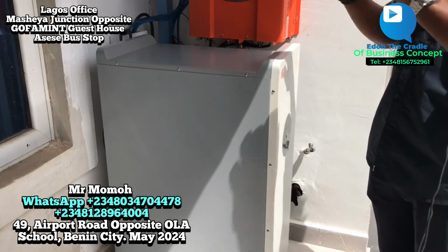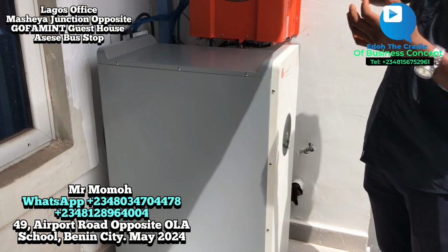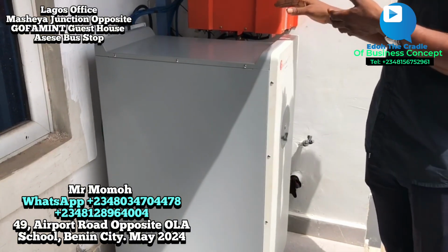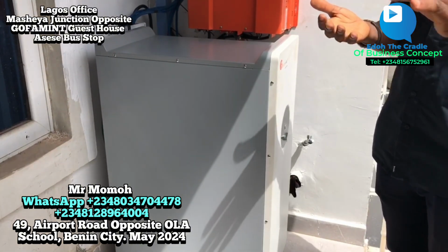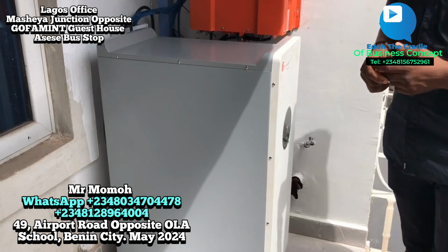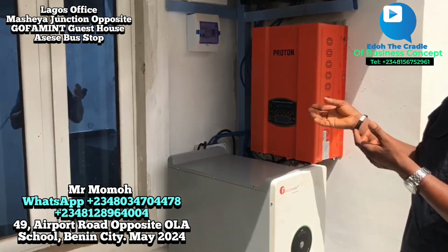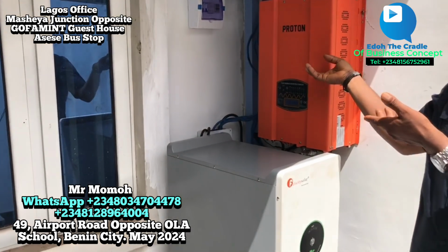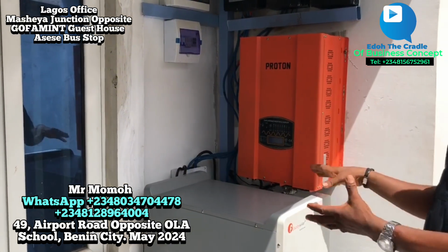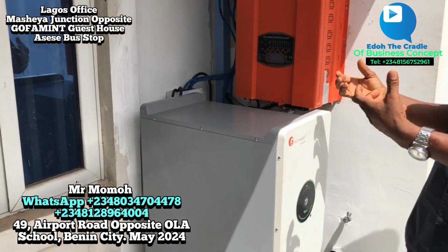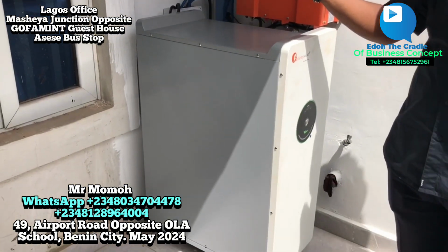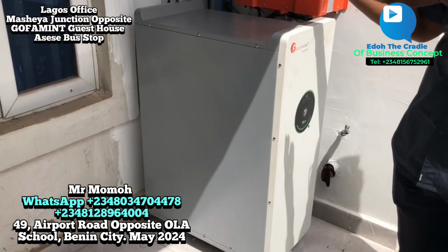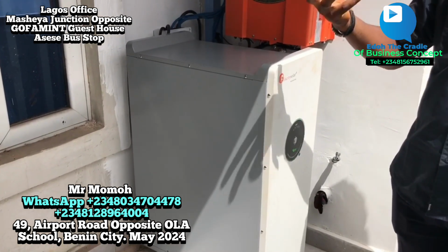The standard is 3.5 kVA. Or even if you decide to put 5 kVA, which is not okay, ensure that you don't exceed a load of more than 2 kilowatts. When you overload the inverter beyond 2 kilowatts, you will see this thing make noise and vibrate. Even clients will hear the sound from inside. So that is that. Another issue is this.